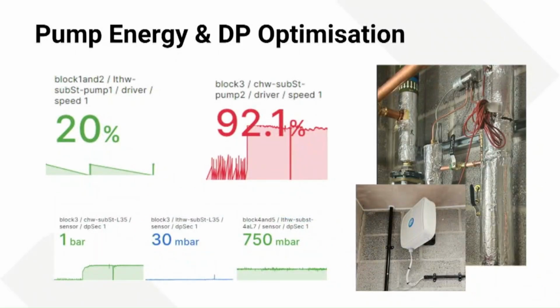Pump energy and DP optimization - this is a function on every heat network. It's common that it doesn't run well. There are some keys to getting it right: first is the correct choice of sensor, second is the correct choice of communications to get the data back to the plant room, and third is having the correct BMS control schedules to actually do the pump control.